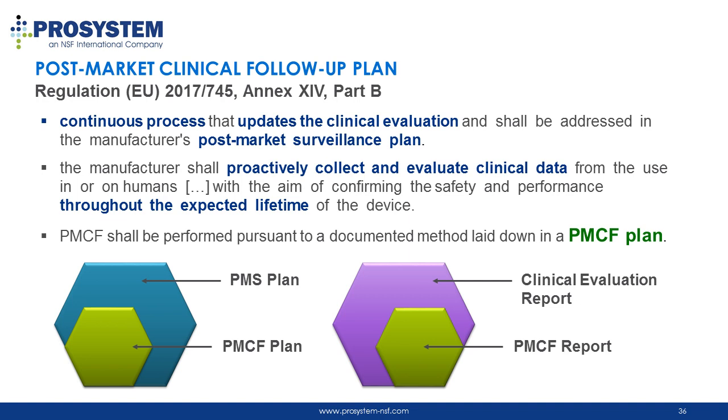Importantly, PMCF activities have to be performed according to documented methods laid down in the PMCF plan, which can be a part of the post-market surveillance plan. The PMCF data collected and analyzed should then update the clinical evaluation reports.